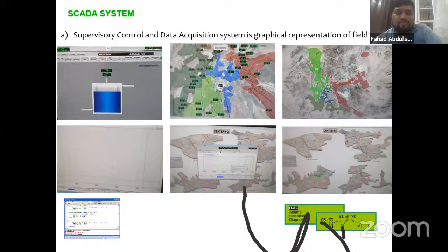SCADA normally stands for Supervisory Control and Data Acquisition System. In simple words, it is a graphical representation of the field. Whatever the sensor senses about temperature or pressure, the SCADA software will display the reading and replicate the field. Whatever is in the field, you can make the graphics the same. It is not a camera system, there are no cameras, these are signals coming from the field. So if any device is faulty or has an issue, it will affect the reading.